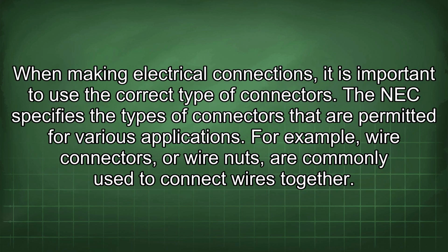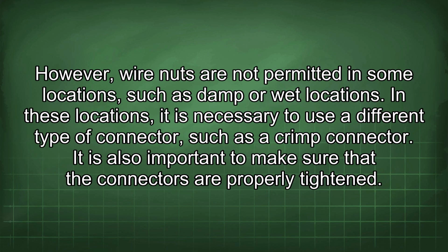When making electrical connections, it is important to use the correct type of connectors. The NEC specifies the types of connectors that are permitted for various applications. For example, wire connectors or wire nuts are commonly used to connect wires together. However, wire nuts are not permitted in some locations, such as damp or wet locations. In these locations, it is necessary to use a different type of connector, such as a crimp connector.